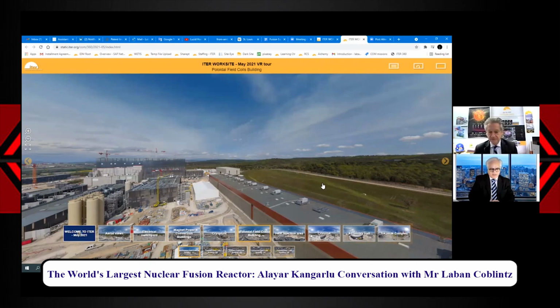So we know that the liquid helium flows through that little hole at the center of the superconducting conductor. Do you have an estimate of how much helium is required to cool down that massive amount of superconducting material after the entire magnet was built? And this whole structure has to be thermally sealed to make sure that you have a very low liquid helium boil off, right? Yeah, we don't want to be replenishing the helium because it's so expensive and also so scarce.